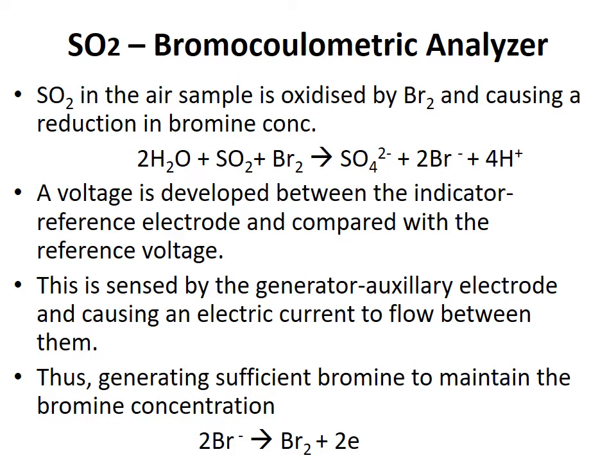The reaction is: 2H₂O + SO₂ + Br₂ → SO₄²⁻ + 2Br⁻ + 4H⁺. The reduction in bromine concentration changes the oxidation-reduction potential of the reagent. A voltage is developed between the indicator electrode and the reference electrode and compared to a reference voltage. The difference is sensed by the auxiliary generator electrode system, causing an electric current to flow and generating sufficient bromine to maintain the original concentration according to: 2Br⁻ → Br₂ + 2e⁻. This current flow is a measure of the SO₂ concentration in the air stream.